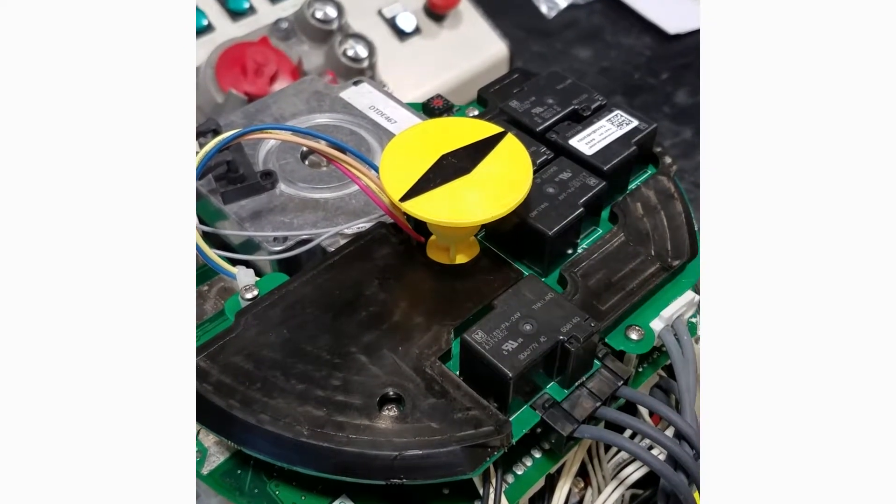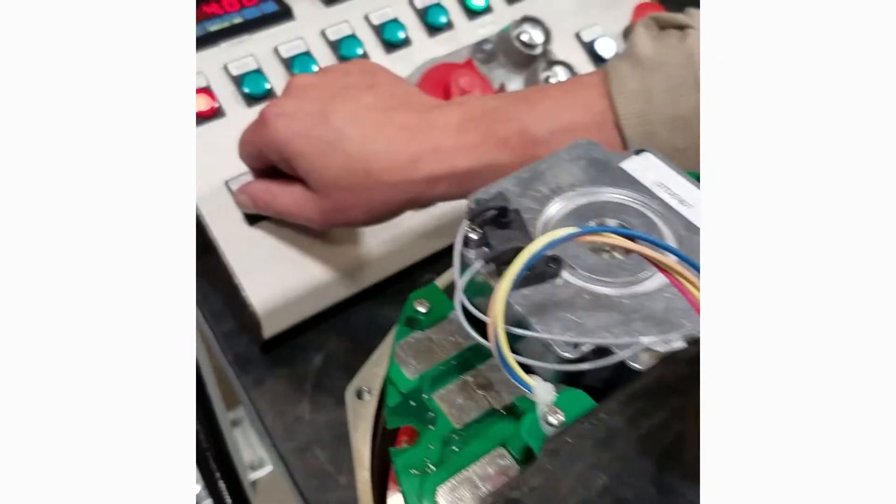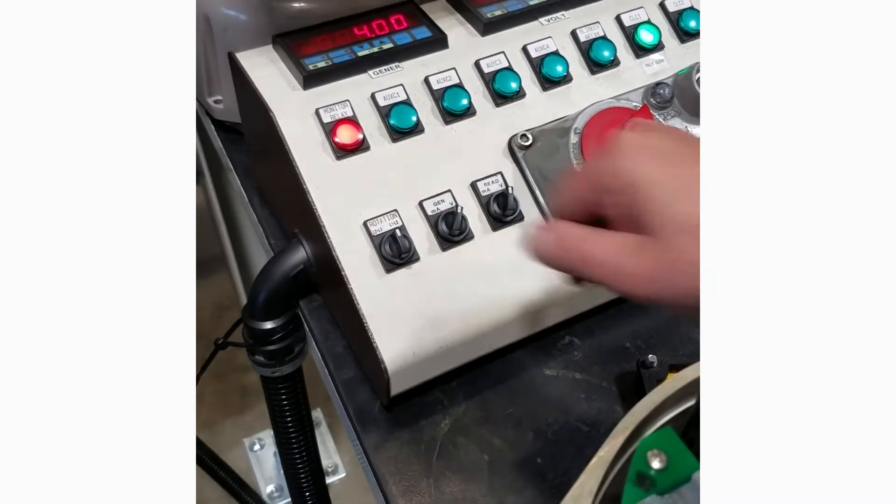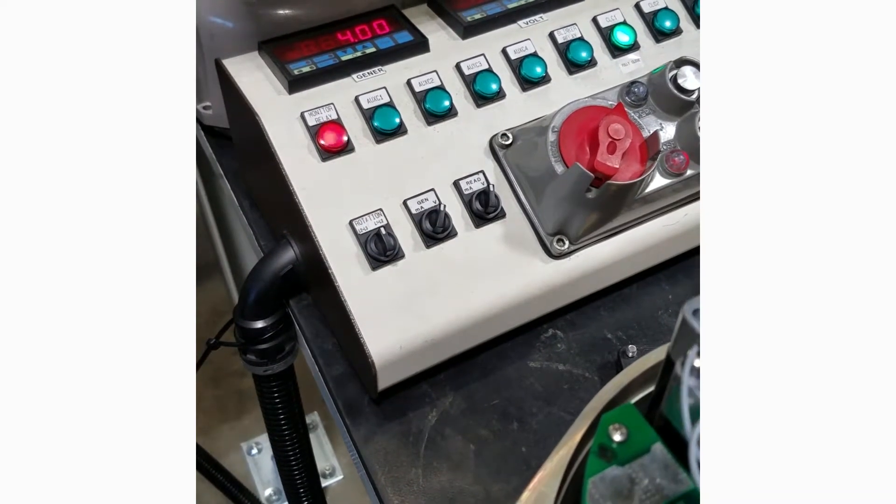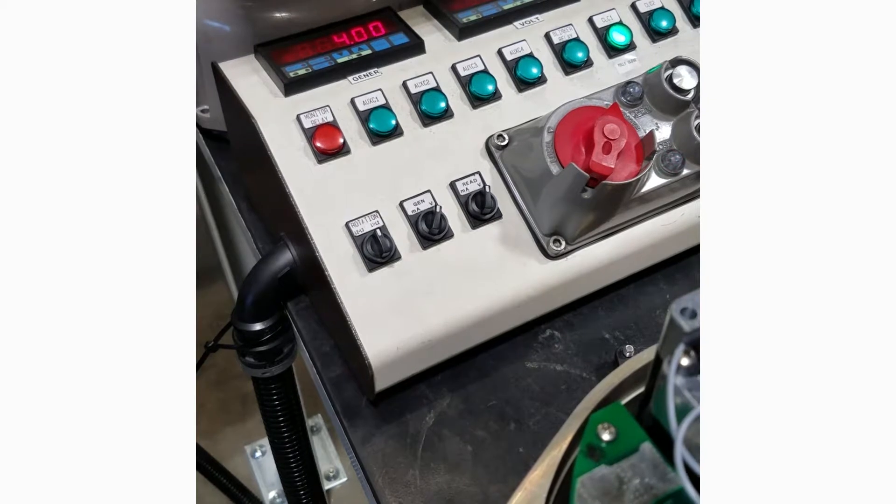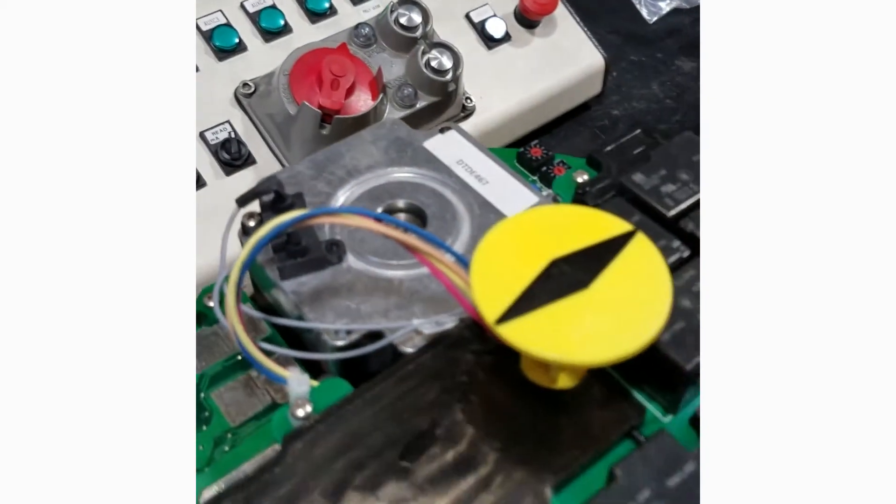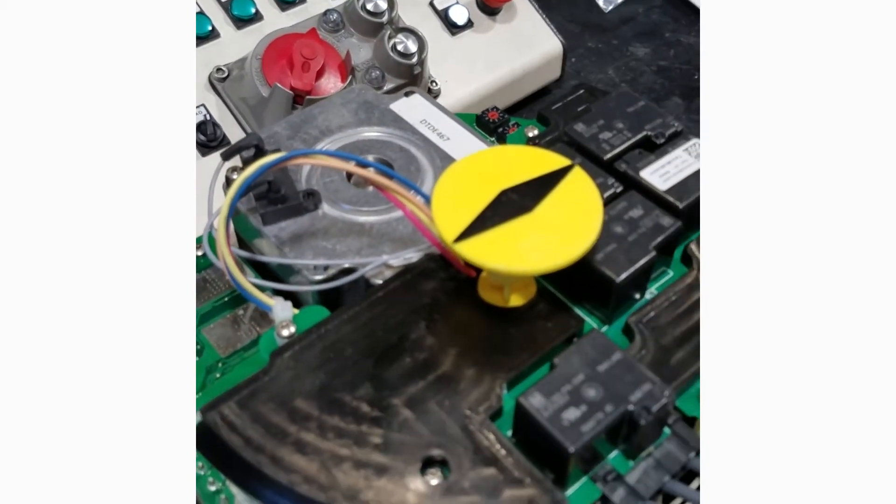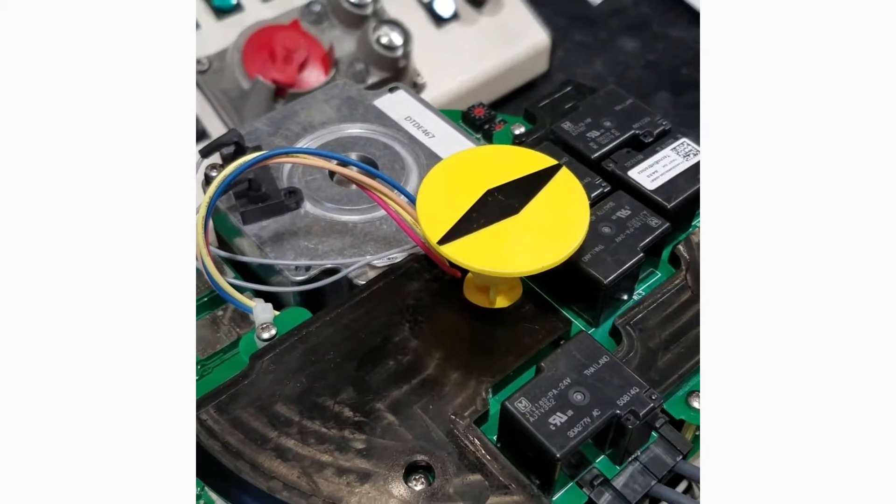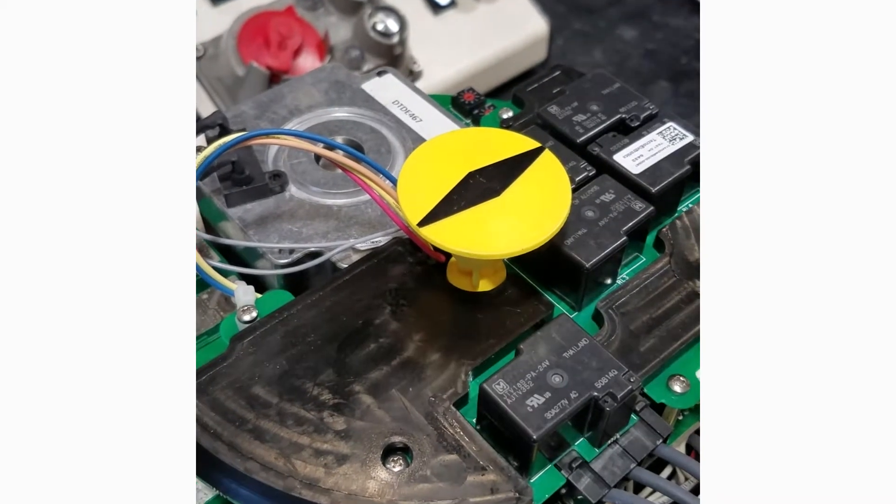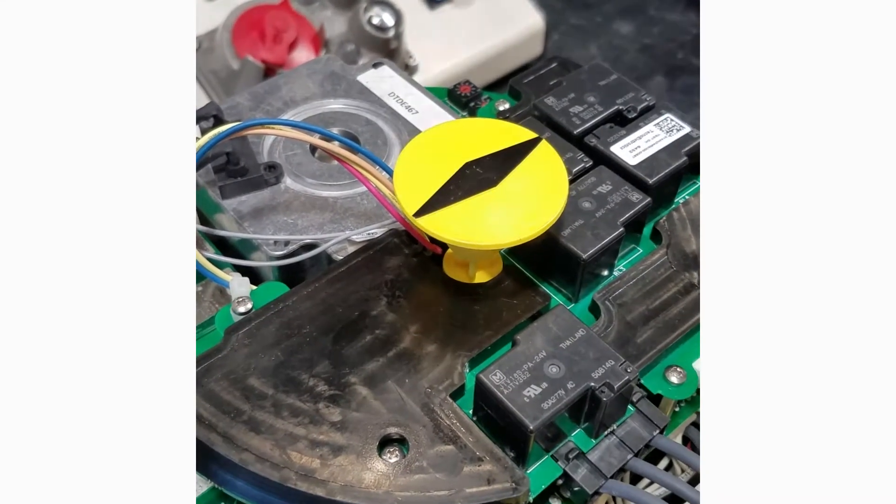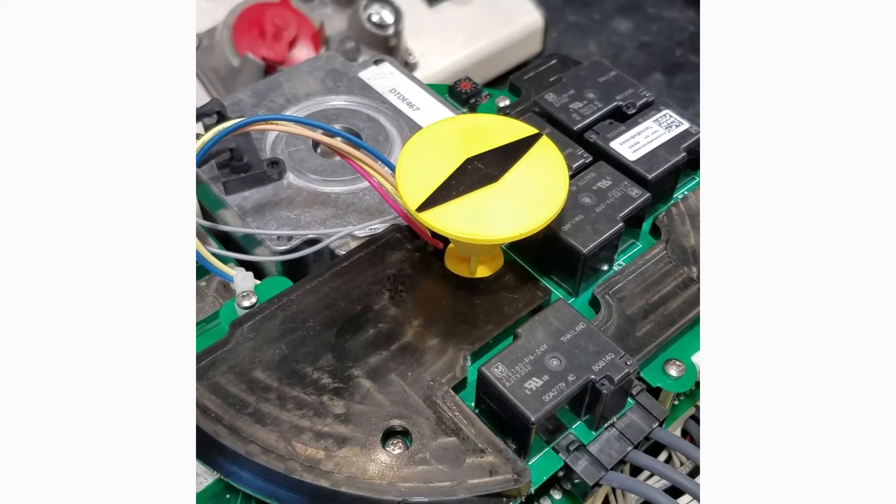The indication relays will latch in last position. So if we remove power from L3 and L1, our indication will not change. If we change the position of the hand wheel and the actuator, the indication will remain as it was when the power was turned off.